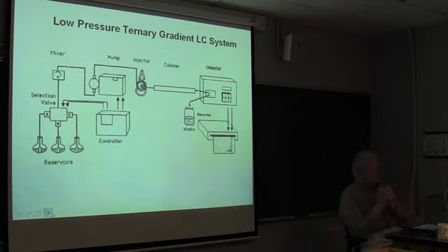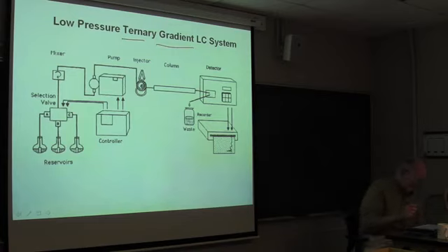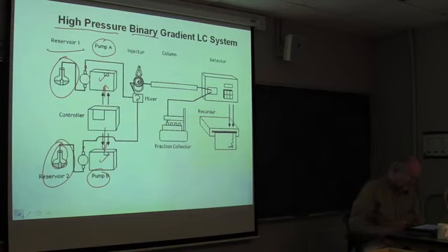So there's another way to do complex gradients, and I'm just illustrating this with a ternary gradient system, but I think most commercial instruments are actually quaternary, meaning they can handle 4 liquids. And it's done in the following way. Oh, whoops, I forgot a very important component here.